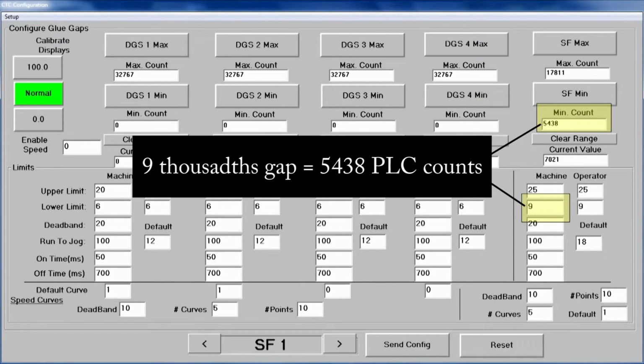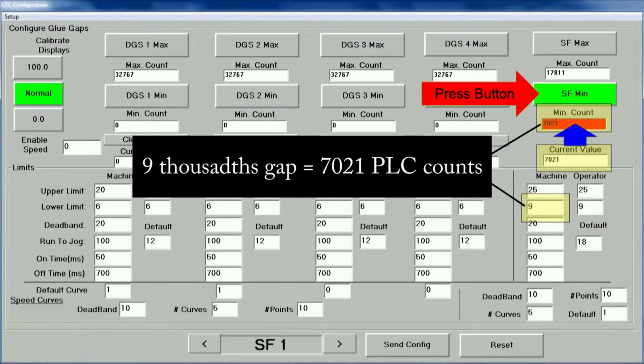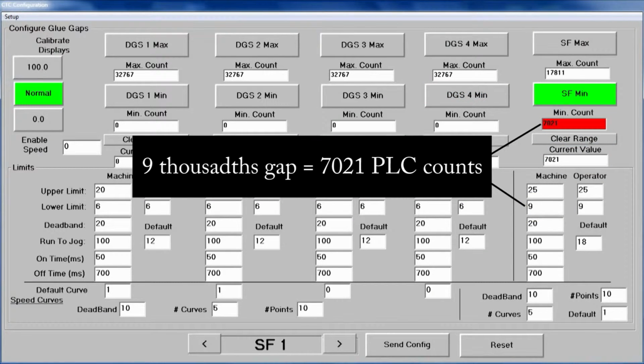The lower limit gap value is directly related to the value in the SF min count field. Currently, the gap is at 9 thousandths when the min count field is 5,438. To calibrate, we need to copy the sensor's current position value into the min count field. Simply press the SF min button. The button turns green and the value turns red, indicating the value has been accepted. Now the gap equals 9 thousandths when the min count field equals 7,021.